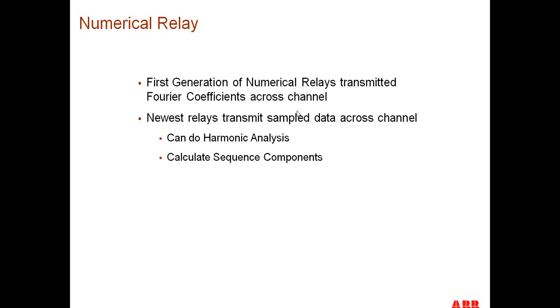In the newest generation of relays, though, instead of sending just Fourier coefficients across the line, we now can send sample data across the line instead. So by sending sample data across the line, we not only know the 60 Hz quantities, but we can do a total harmonic analysis and know such things as the second harmonic and fifth harmonic and all harmonics of that signal, and can also calculate sequence components based on that information. You'll see how we can use that information in a little bit now.